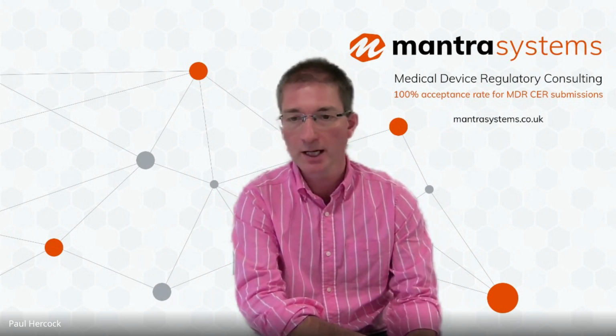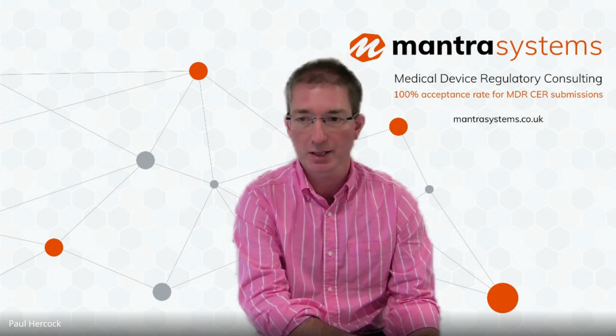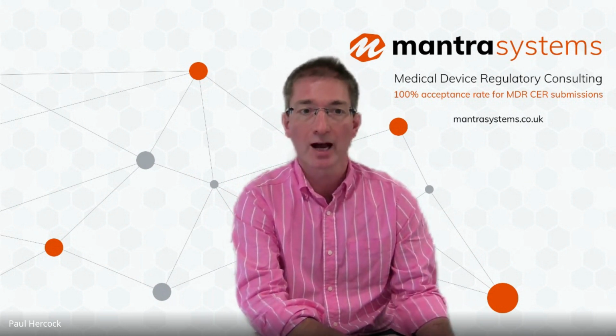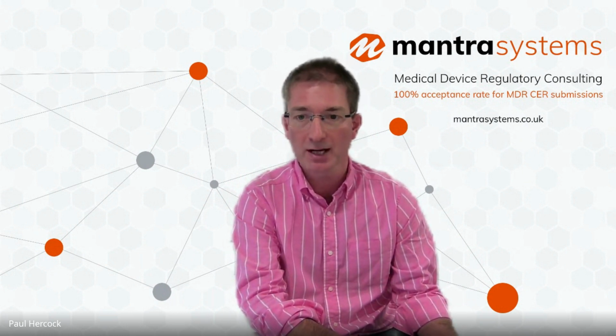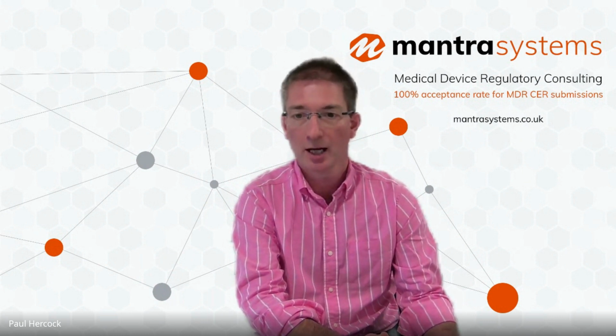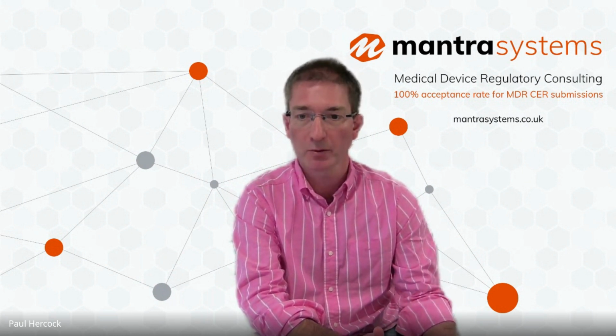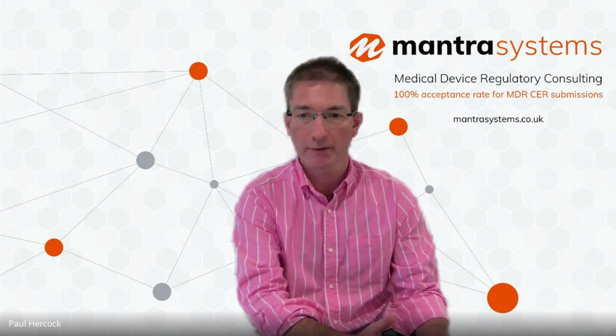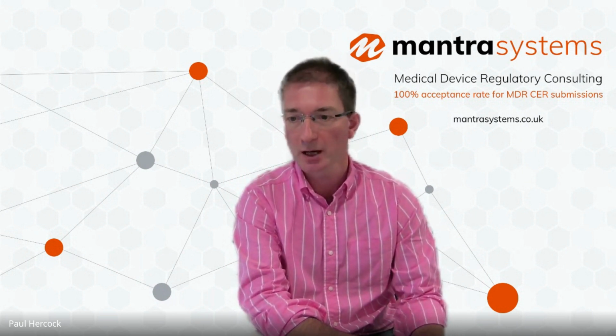So yes, you do need a clinical evaluation, even if your device is a class 1. That said, it doesn't have to go into the same level of detail as if it's a class 3, but it's still a big, significant piece of work that needs to be done properly. And if done properly, it actually has significant benefits beyond just ticking a box.